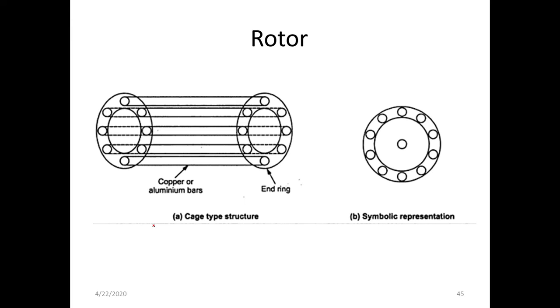Then the rotor. The rotor construction is the squirrel cage type. In this type of rotor it consists of long copper or aluminum bars which are placed in the slots. The bars are permanently shorted at both ends with the help of end rings. As the bars are permanently shorted, the entire resistance is very small.